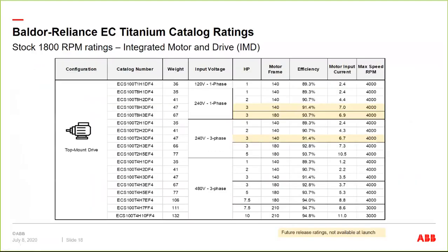So here's our ratings again, starting at 89 all the way up to 95% efficiency. Now this is for the motor only. And you're going to see, in our testing, about 1.5 to 1.8% additional losses in the drive. So when you add the drive in, you need to take out another 1.8% on the front end of the drive and losses there. But in a lot of cases, because this is at IE5 plus efficiency, even with the losses of the drive, we're above the IE5 efficiency level.